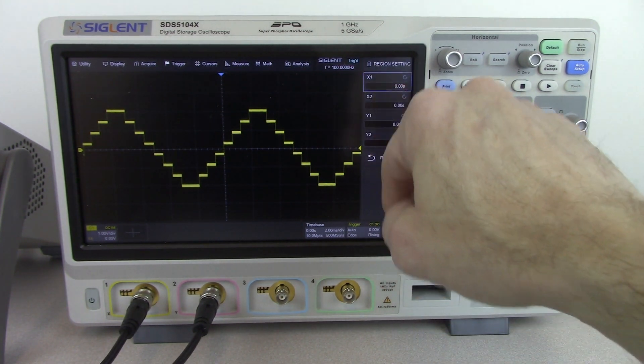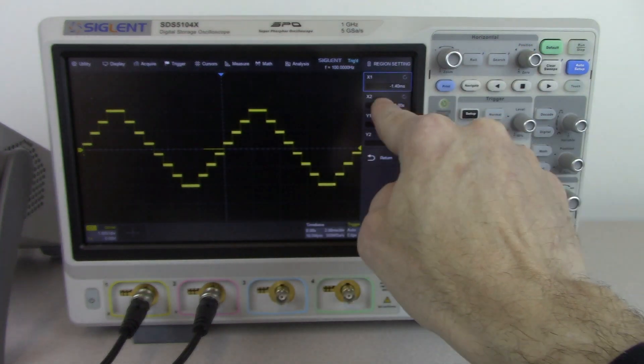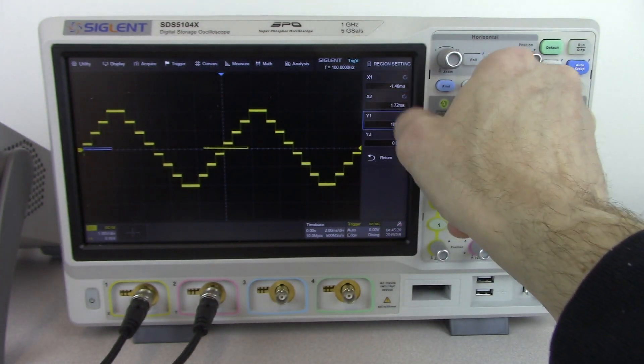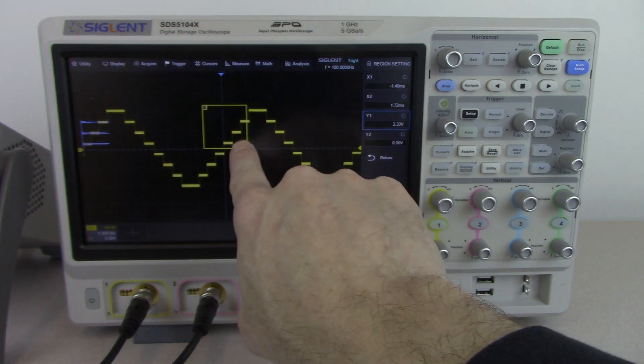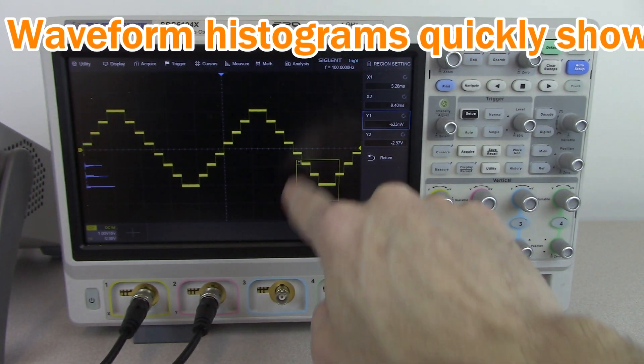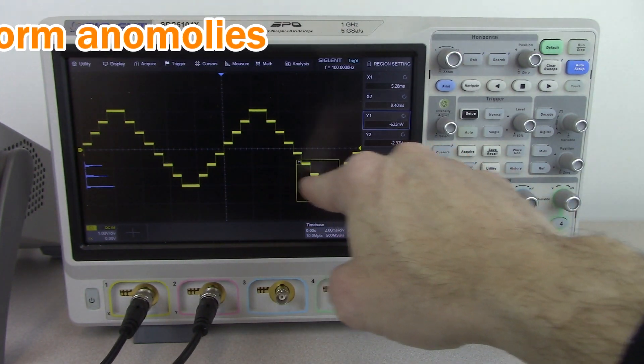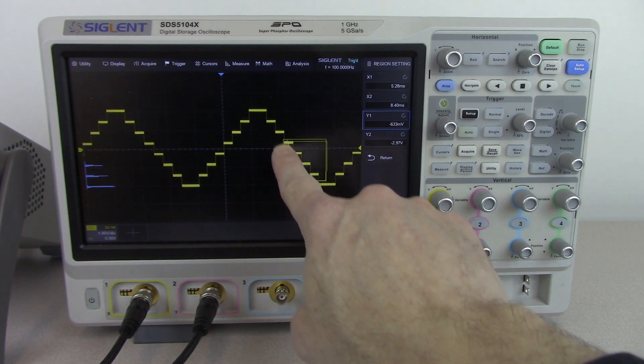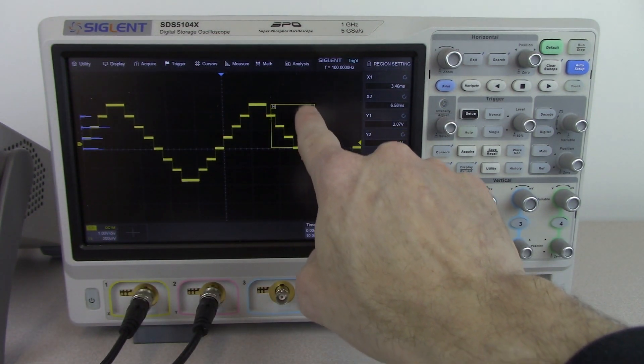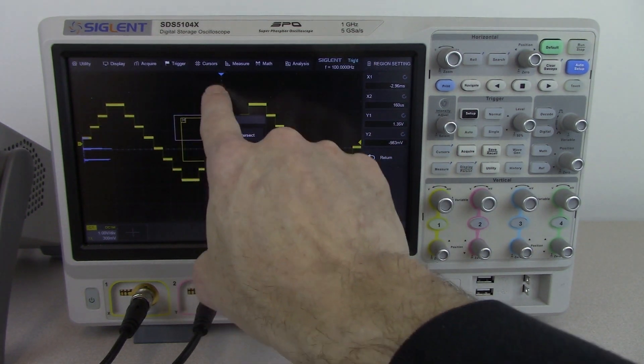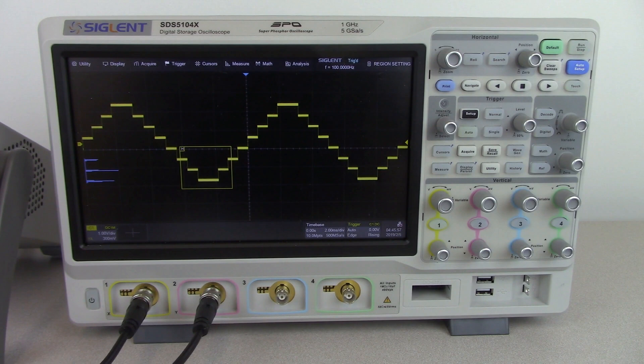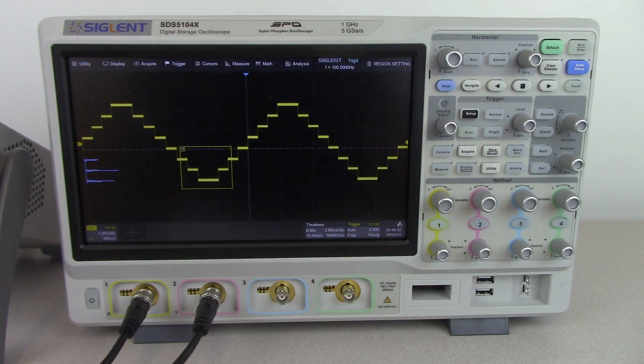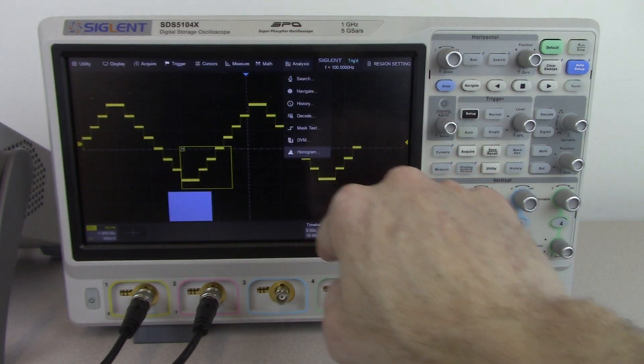Go to region setting. Now I'm going to select X and you'll see a small yellow box come out here, a small yellow line that denotes that X axis. Now let's go to the Y and you'll see as I start to go up. At each individual bin location, we're going to get some statistics based on its location. We can move that around and we can now tell how often these values are getting hit. You'll see these pixels are going to have a lot more statistical hits here in those bins than something up here. We can actually move that around anywhere we would like and we can grab onto two of those and we'll see the statistics. If we had an event that occurred infrequently, we would see one or two small bins here. If we had jitter or some type of mistake in our pulse, we'd be able to acquire that information very quickly from the display. We can use horizontal as well as vertical in this case.